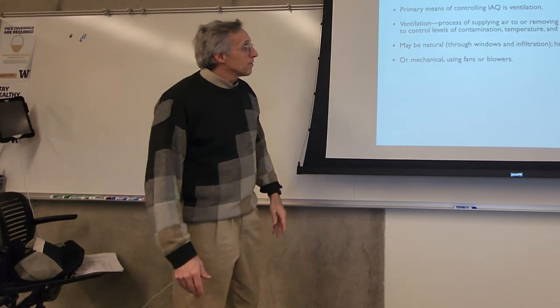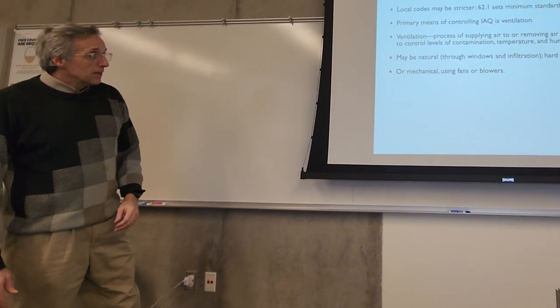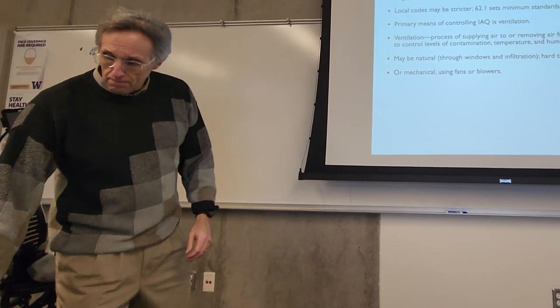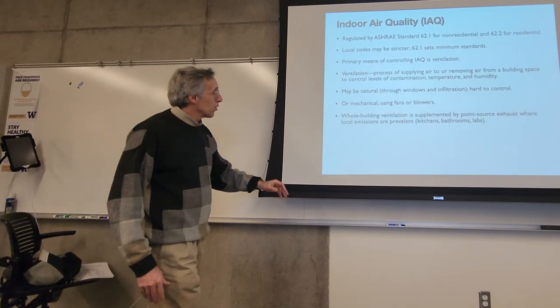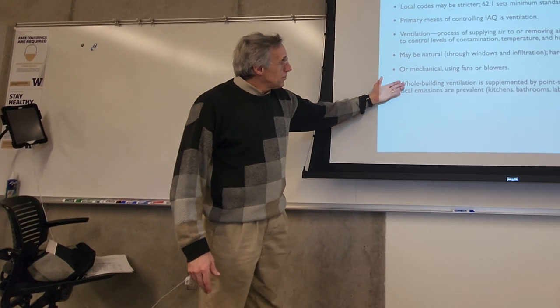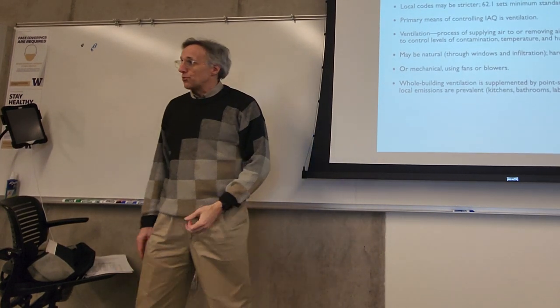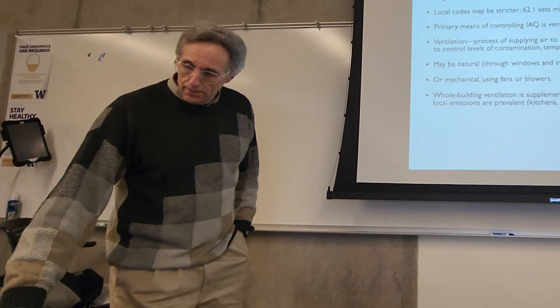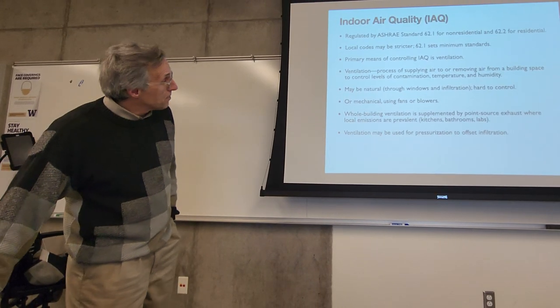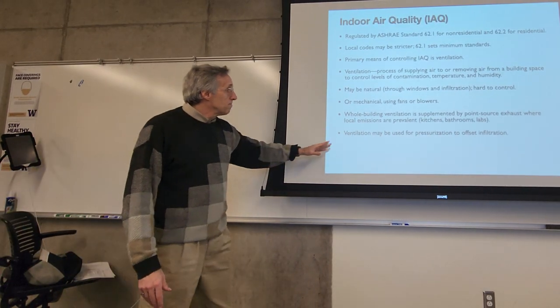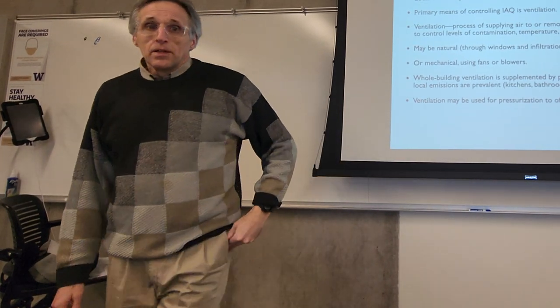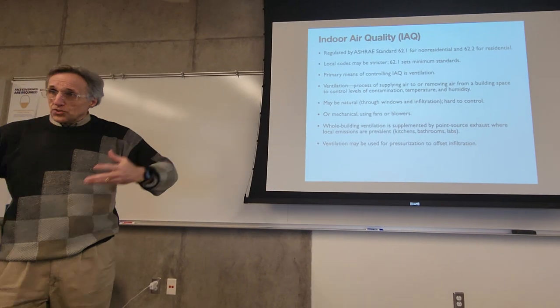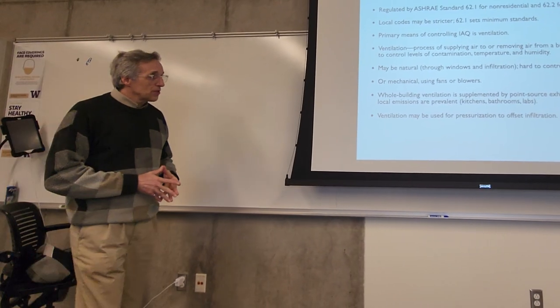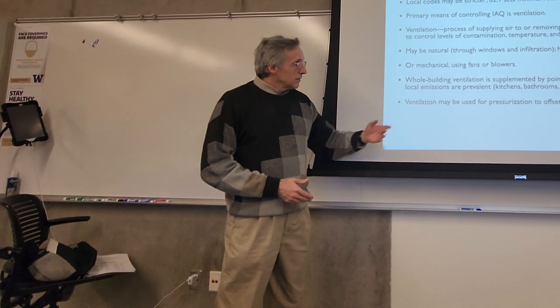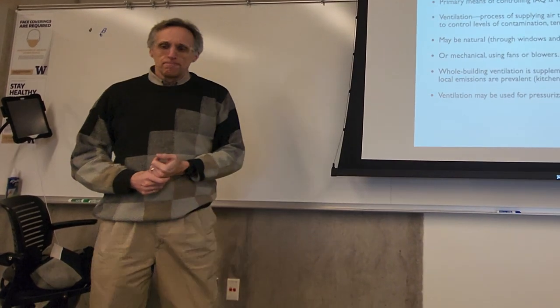You can also use natural ventilation and mechanical ventilation, using, of course, fans and blowers. And then for specialized areas, kitchens and bathrooms have to have extra ventilation to remove odors and moisture and things like that. You can use ventilation for pressurization, if you don't want outside air coming in. So you pressurize the space. You'll see that in a hospital, for example.